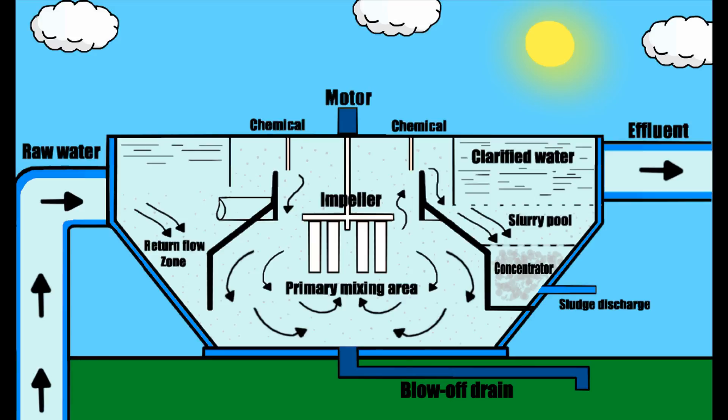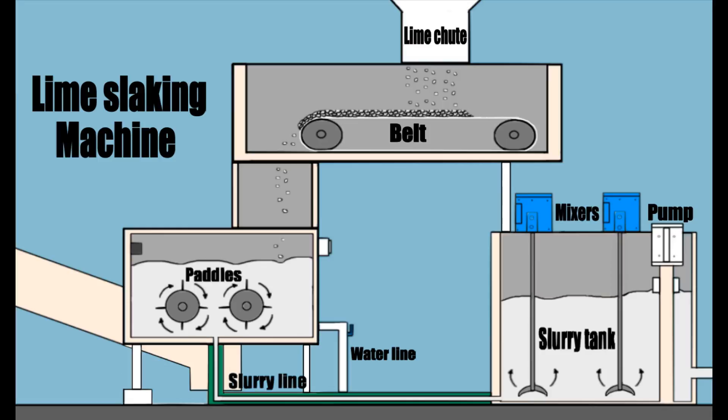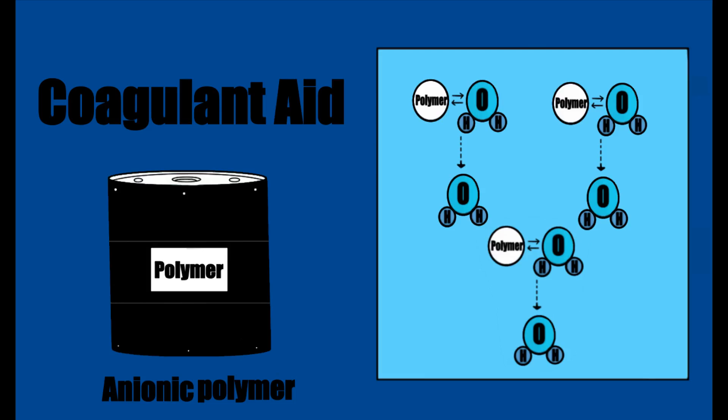This is a lime slurry created in the slaking process of one of our two lime slaking machines. This lime slurry, along with the polymer that is added to bond the lime particles together and cause them to settle out, effectively reduces the hardness of the raw water.